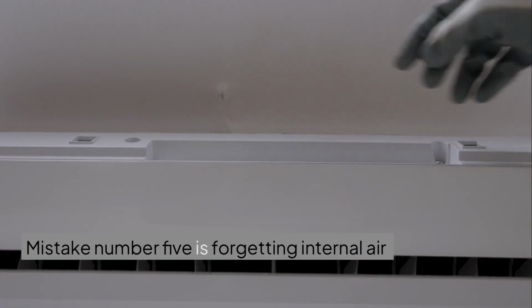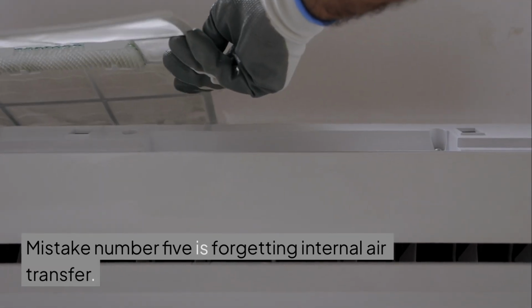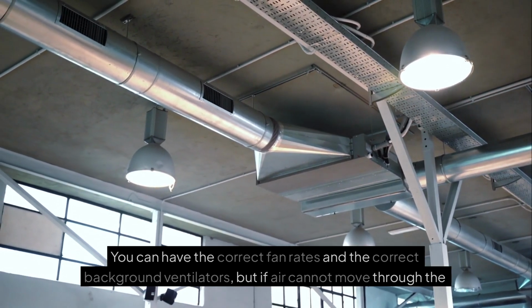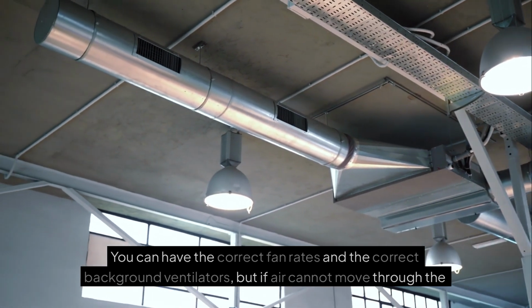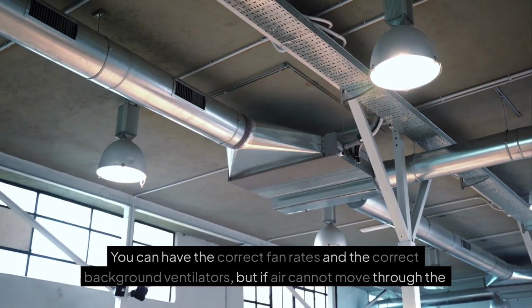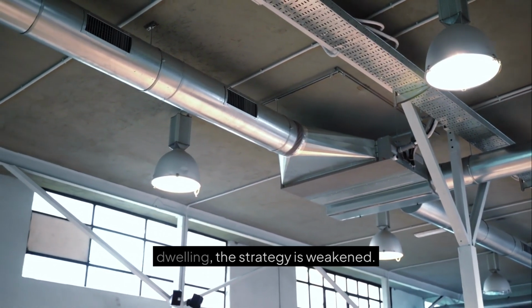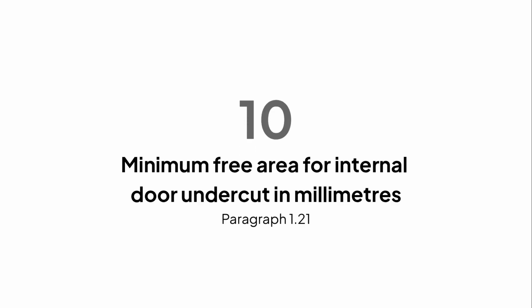Mistake number 5 is forgetting internal air transfer. You can have the correct fan rates and the correct background ventilators, but if air cannot move through the dwelling, the strategy is weakened. Paragraph 1.21 requires a minimum free area equivalent to a 10 mm undercut in a 760 mm wide internal door, with the actual undercut depending on whether the floor finish has been fitted.